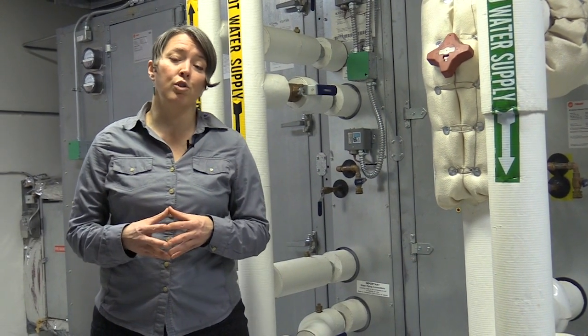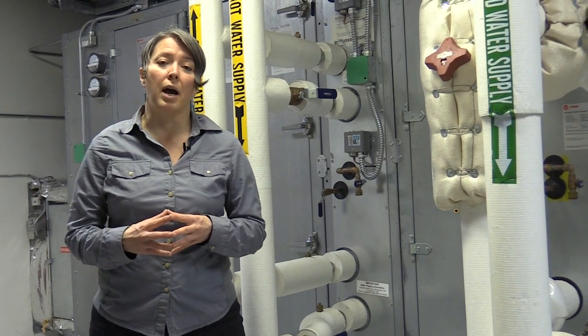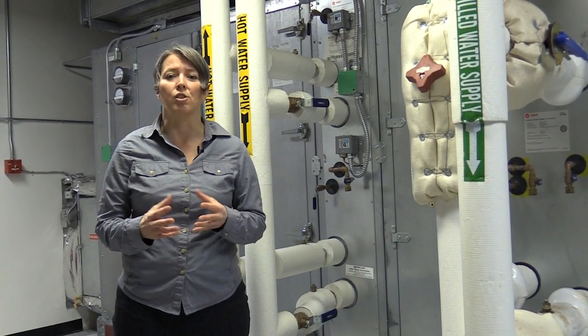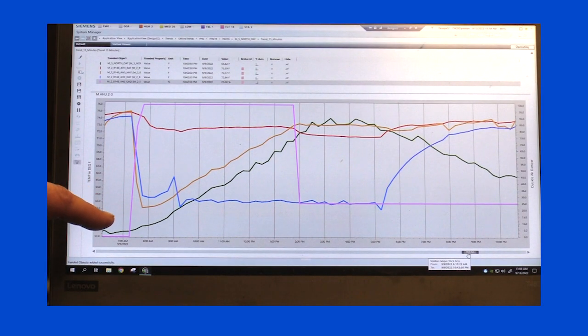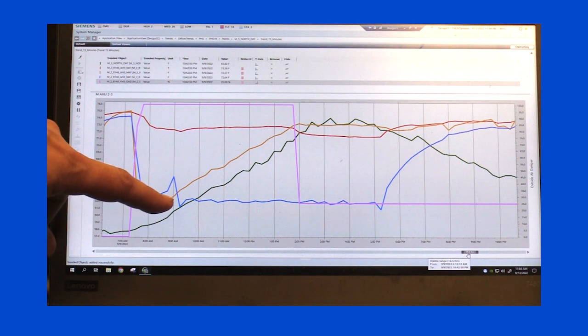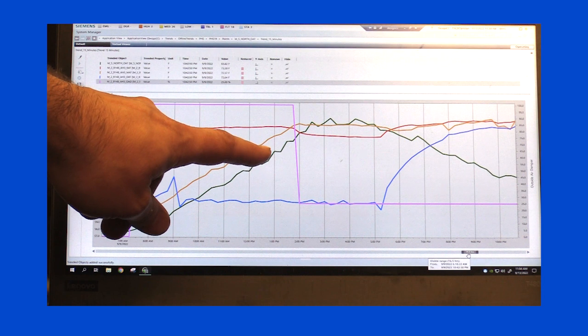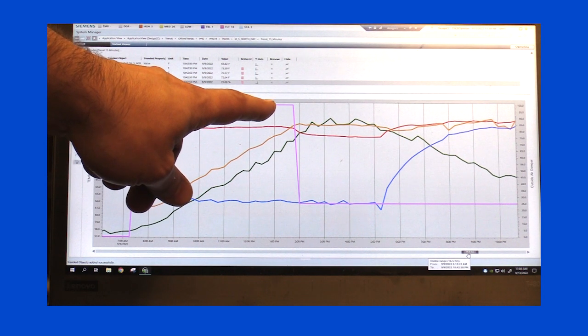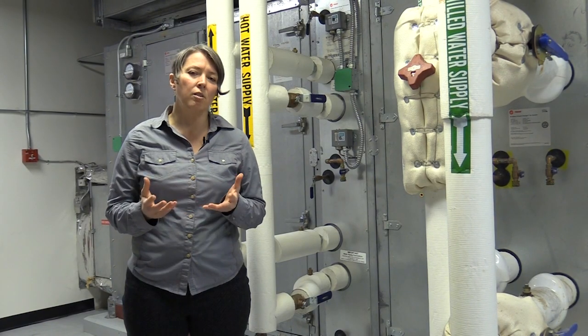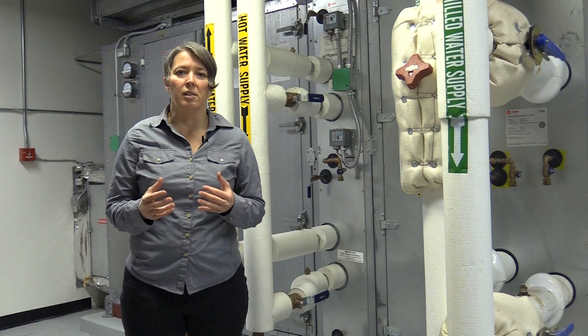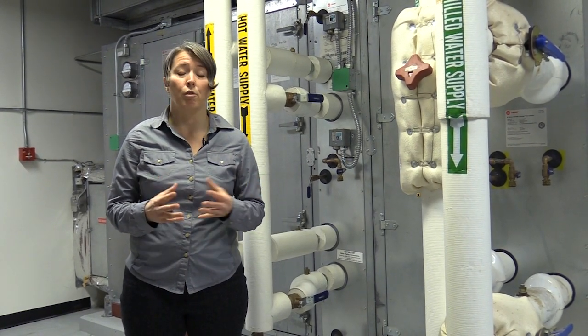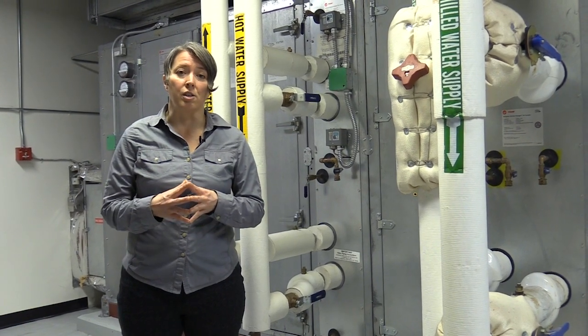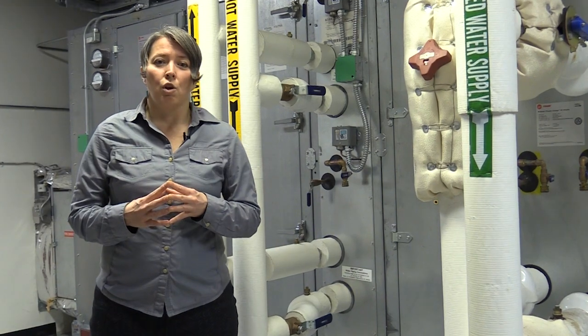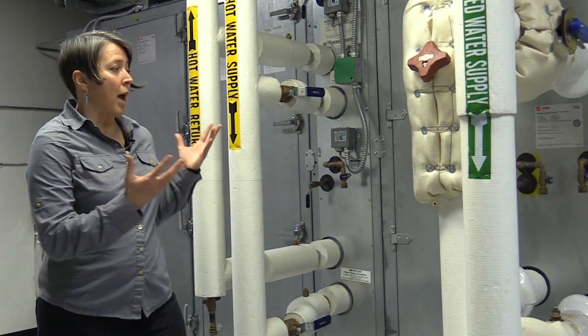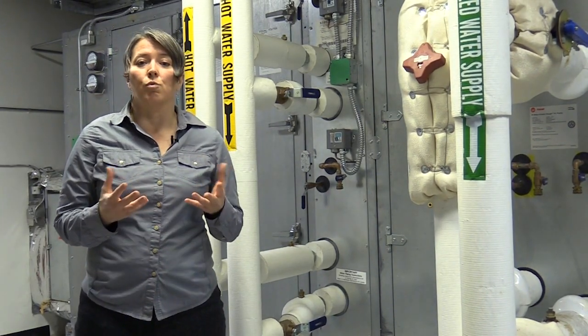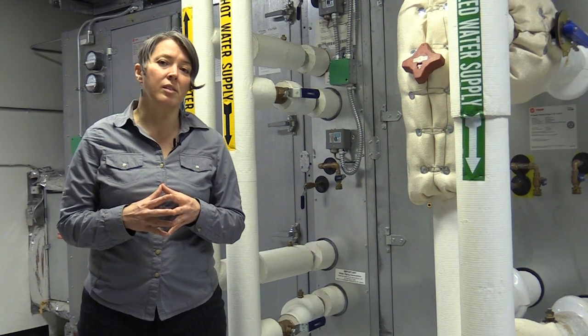In more sophisticated systems, you have the control being done by a building automation system using direct digital controls. And these can be remotely monitored, and trend logs can be set up to view the data over time and verify or identify that the strategies are working as intended. But data loggers can be really useful in this situation as well, as a double check to make sure that sensors are calibrated correctly and there aren't other anomalies that you might miss on the building automation system. So in this video, we'll look at this packaged air handler unit that is controlled by a building automation system. But the concept is the same for standalone systems.